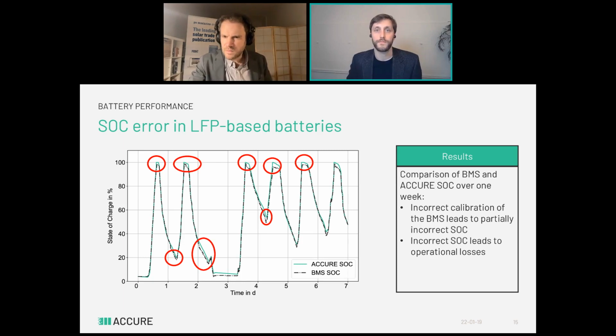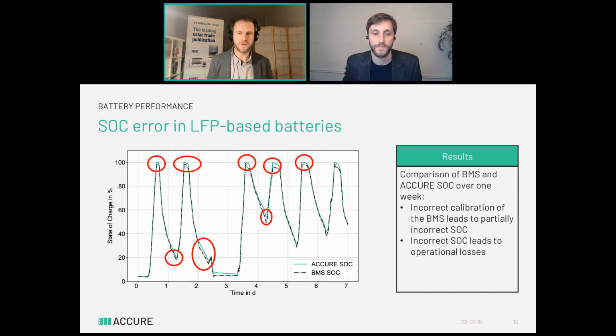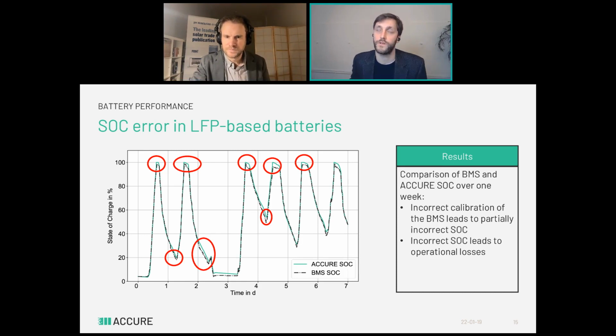What is the benchmark used to determine the SOC error, and what is the error in millivolts? LFP lithium-ion batteries have a very flat SOC to OCV curve - the open circuit voltage curve is really flat in the middle, which makes it difficult to use. There are two ways to calculate state of charge: one based on current, one based on voltage. If you have a flat curve, there's a very low correlation between voltage and state of charge, which makes this more challenging.